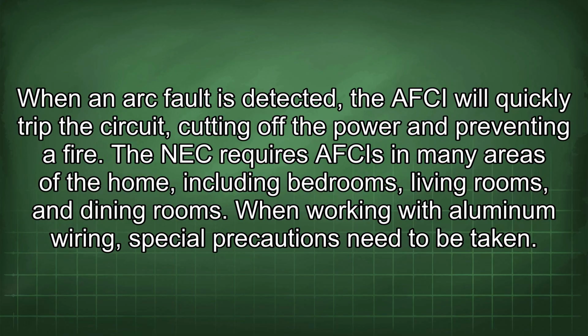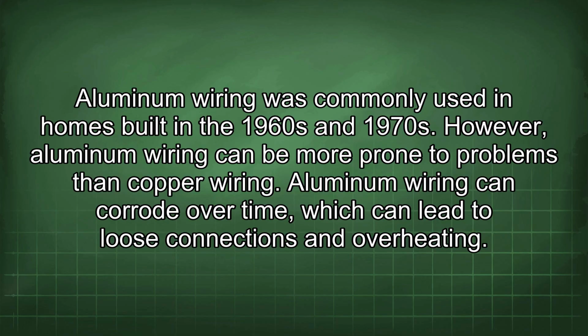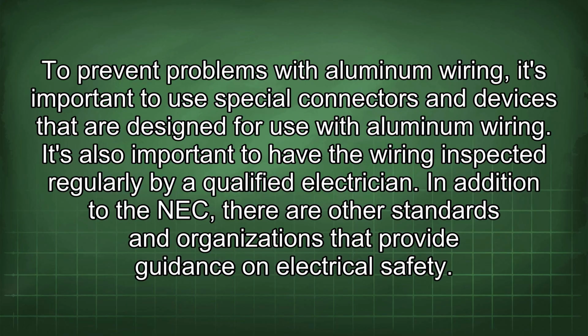When working with aluminum wiring, special precautions need to be taken. Aluminum wiring was commonly used in homes built in the 1960s and 1970s. However, aluminum wiring can be more prone to problems than copper wiring. Aluminum wiring can corrode over time, which can lead to loose connections and overheating. To prevent problems with aluminum wiring, it's important to use special connectors and devices that are designed for use with aluminum wiring. It's also important to have the wiring inspected regularly by a qualified electrician.